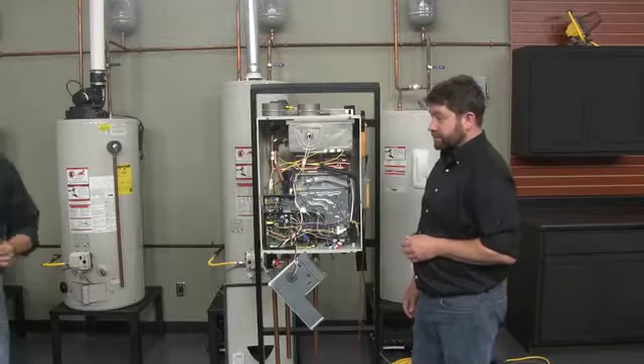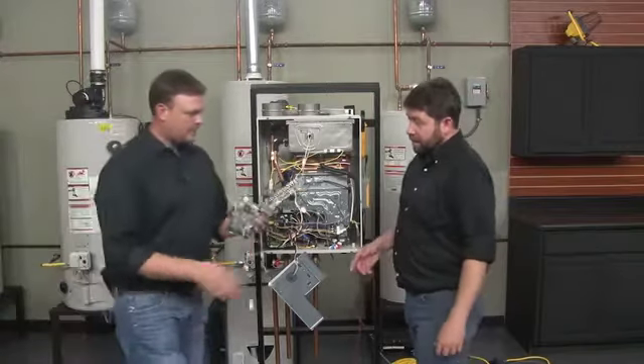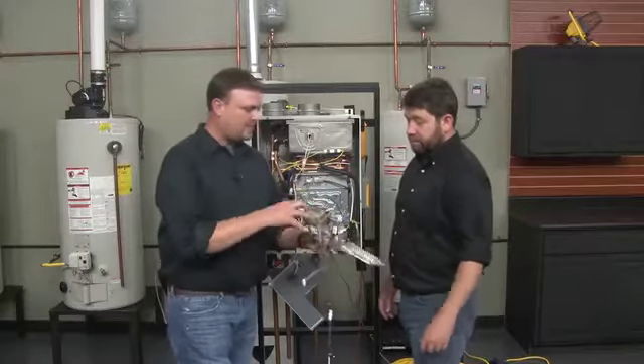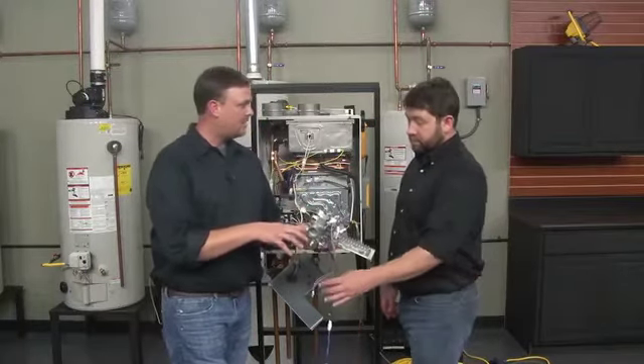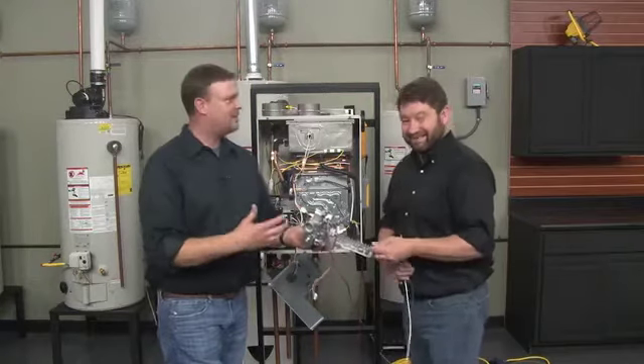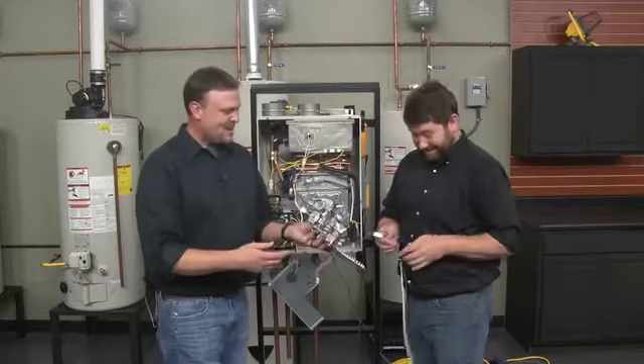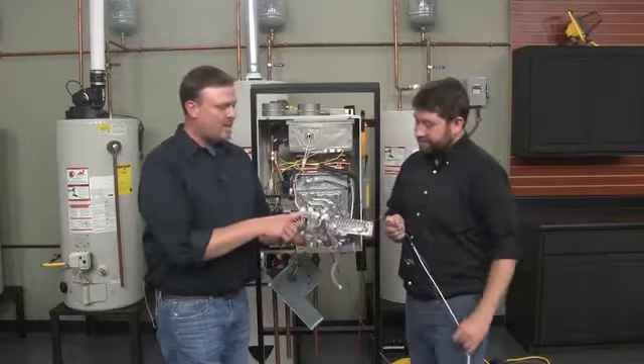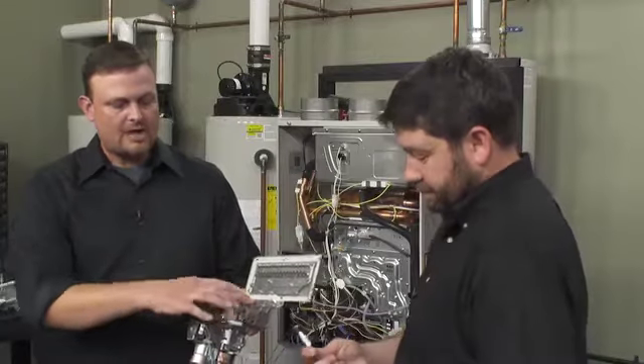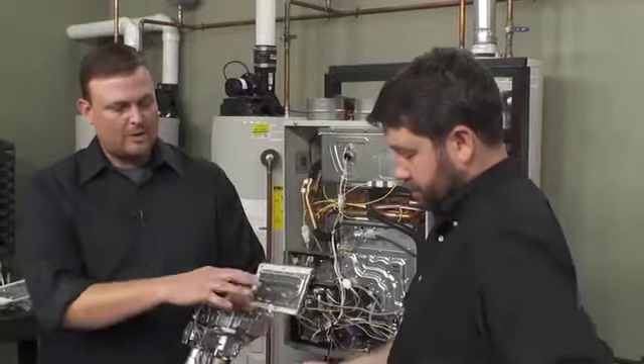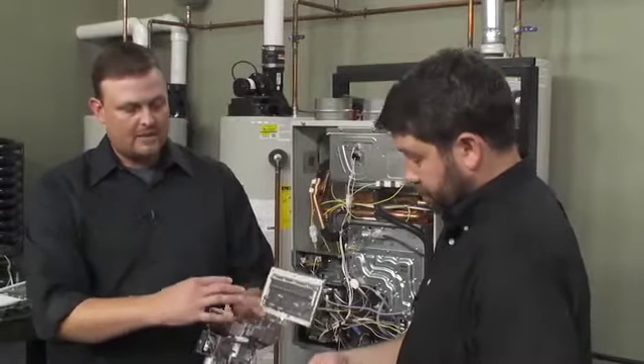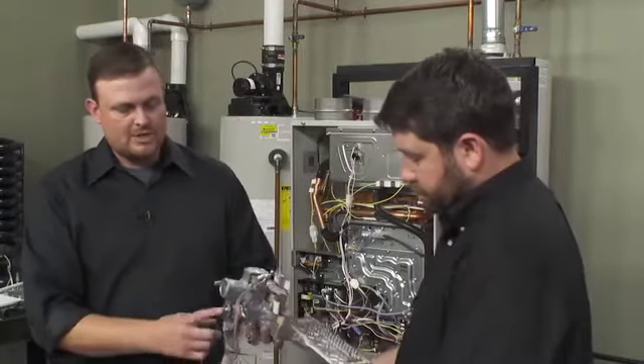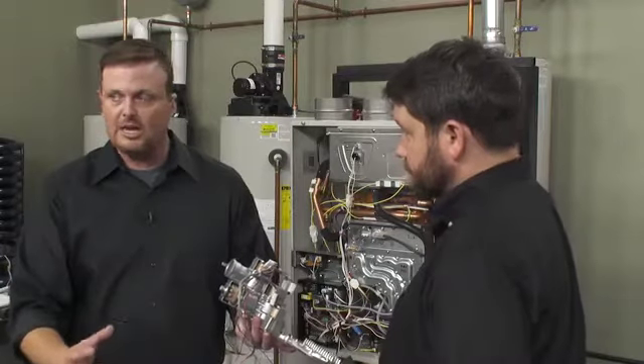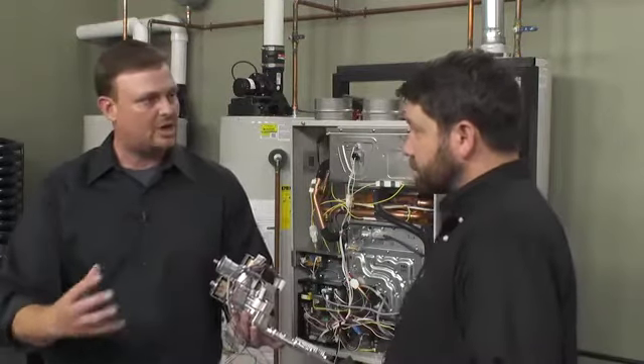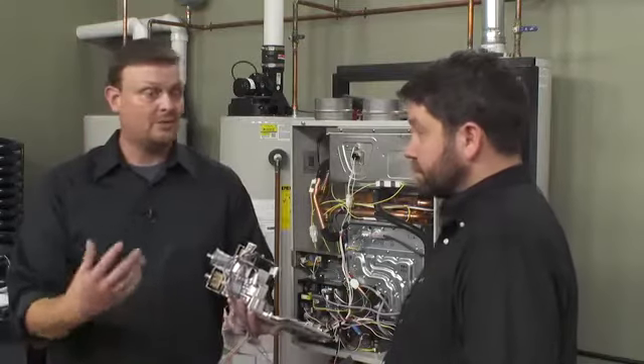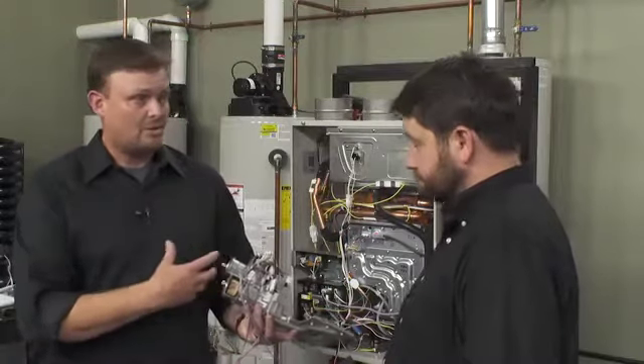So you've got a gas valve here, and this is really cool. This is the manifold and the gas valve. You've got 5 solenoid valves on this gas valve. You've got a modulating solenoid valve, a main solenoid valve, and then 3 solenoid valves that open up chambers and allow the gas to come in. But this modulating solenoid valve is what's going to modulate it anywhere between 15,000 BTU and 199,000 BTU. And that's really based on demand or flow.